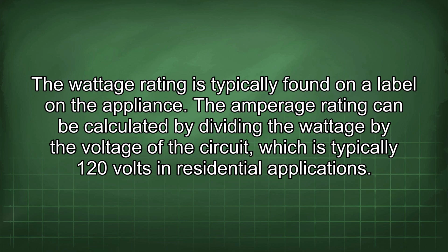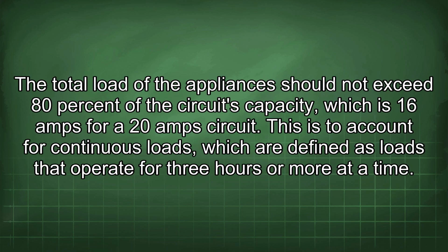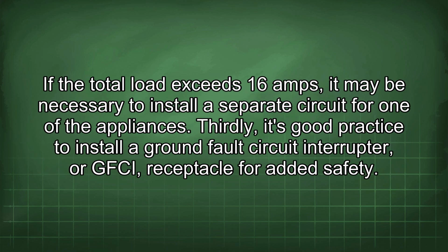The amperage rating can be calculated by dividing the wattage by the voltage of the circuit, which is typically 120 volts in residential applications. The total load of the appliances should not exceed 80% of the circuit's capacity, which is 16 amps for a 20-amp circuit. This is to account for continuous loads, which are defined as loads that operate for 3 hours or more at a time.